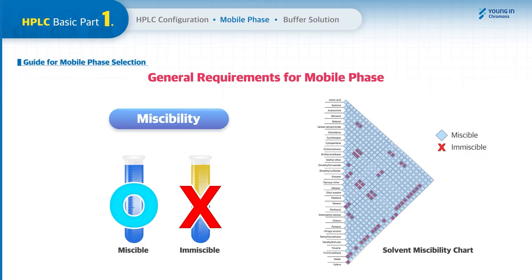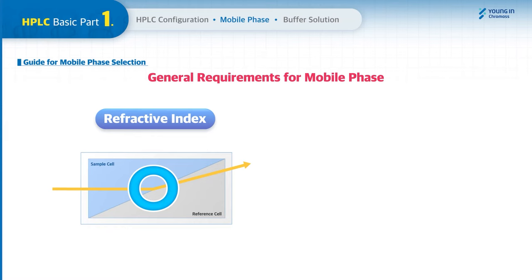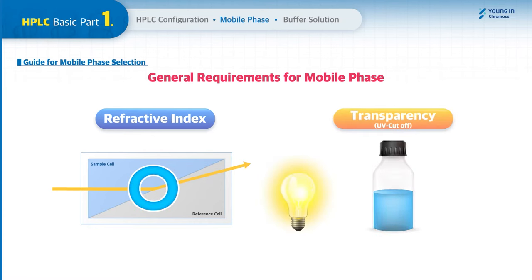There is a solvent miscibility chart you can refer to which shows miscibility between general solvents for HPLC. The refractive index should be considered when using an RI detector — if the RI of the mobile phase is the same as one of the analytes, no detection will occur. The mobile phase without sample must also transmit sufficiently at the wavelength used for detection, which relates to the UV cutoff required for use of a UV detector. The UV cutoff of the mobile phase should be lower than that of the analytes.